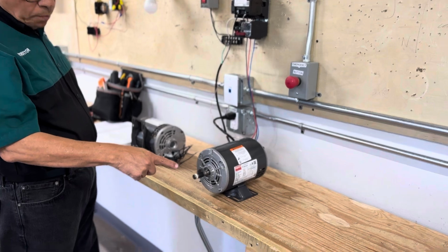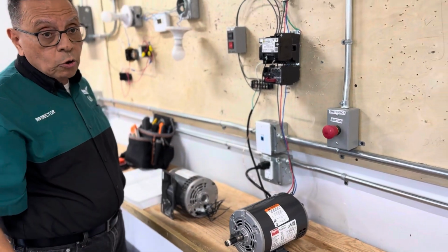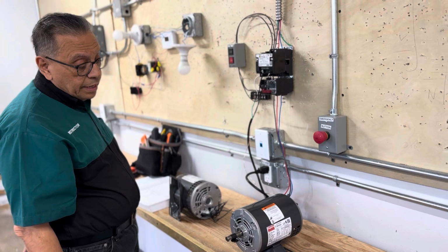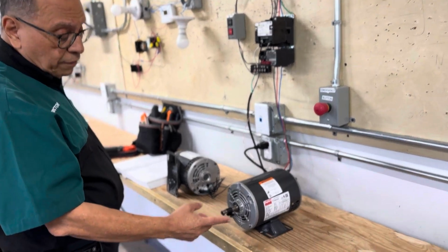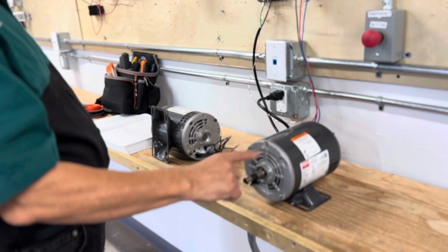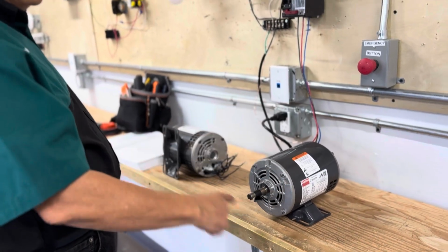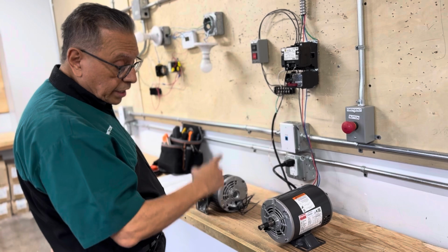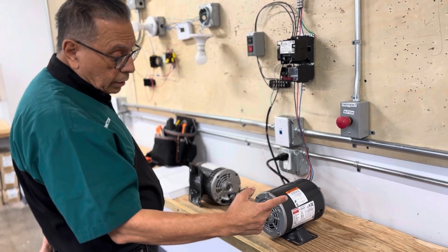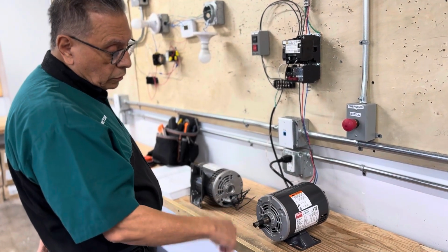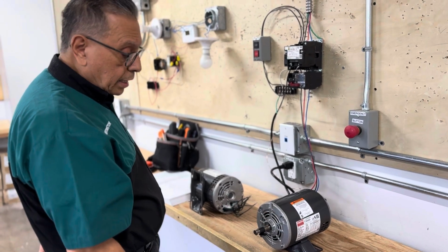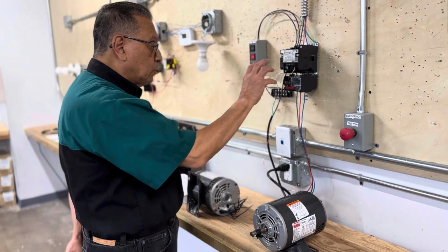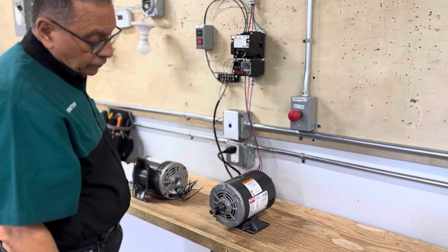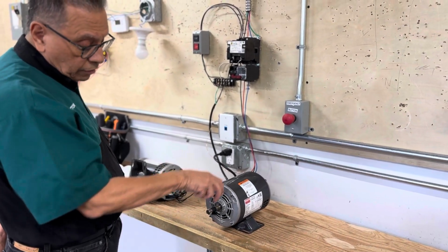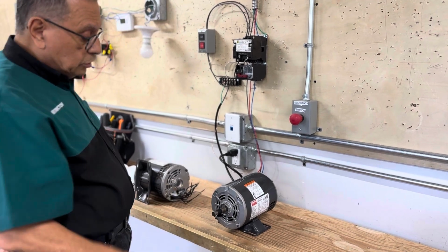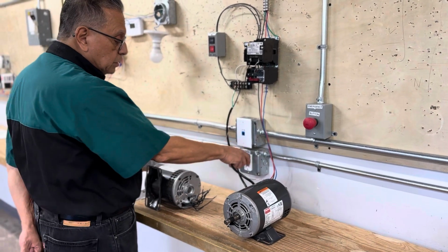For example, it's stopping. If I start it now, I will be overloading the electrical motor, because the shaft is spinning in the opposite direction. Then I try to restart it, and the shaft will try to go clockwise while it's stopping counterclockwise. That will be an overload that I apply to my stator, in addition to the weight of the shaft because of gravity. So it's important that we take this aspect into consideration.